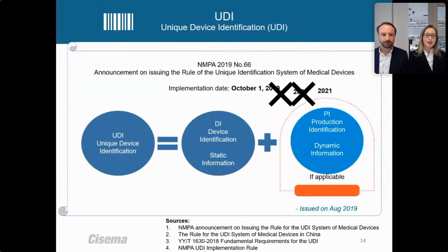And on the slide, you can see what the UDI is made up of. According to the risk level and the traceability requirements of a medical device, the composition of a UDI is shown on the slide. The UDI can be made up either of a DI alone, the device identification, or by a combination of DI and PI, PI standing for production information. Just to explain those two terms a little bit further, DI consists of static information. So that contains a manufacturer identification code, for instance, so the license holder, and the product code, identifying the model, specification and packaging. And then on the other hand, the PI, the production information, is more dynamic information. This includes codes related to the production process, the serial and batch number, or the production date and expiration date. And this is not necessarily mandatory.